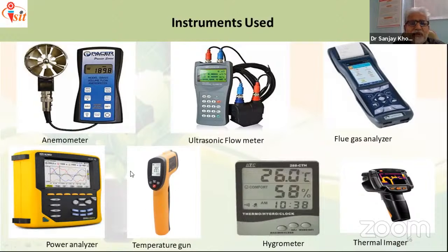Now this is the temperature gun. It has become so popular because of COVID, as everywhere we are measuring temperatures. In a similar way, it is essential to measure the temperature of a number of appliances. In addition to the temperature gun, nowadays we have purchased another state-of-the-art instrument, that is a thermal imager. With the temperature gun you get the temperature at a point, but with the thermal imager you get a thermal image, or contours, showing the temperature on the outside surface of the motor and on different pipes through which hot fluid or steam is flowing. This gives an idea about at what temperature the machines and motors are working. Especially for electric motors, if the temperature keeps increasing, it will affect the insulation inside the motors and their life gets drastically reduced. So here these thermal imagers are very important.